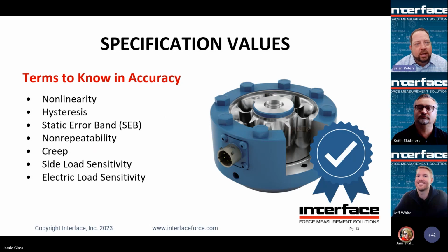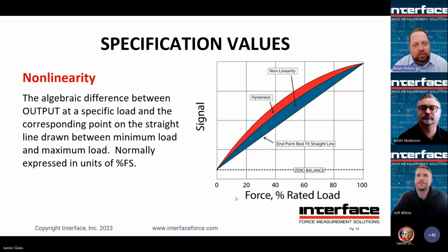All right, so looking at accuracy here, under the accuracy section, these are the common specifications you're going to see on Interface data sheets as well as most other sensors. So: nonlinearity, hysteresis, static error band, non-repeatability, creep, side load sensitivity, and eccentric load sensitivity. Now, those last two you may not see on most other product data sheets, and you'll see them on all of our moment compensated load cell products. So, all right, let's go to nonlinearity.